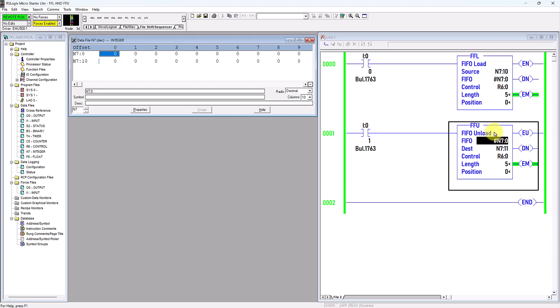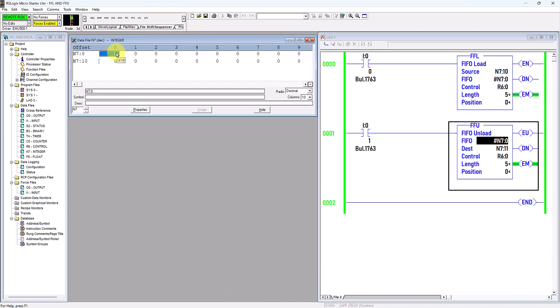As for FFU, or First In First Out Unload instruction — when being energized, the value from the FIFO file address N7:0, which has about 5 words of length, will be unloaded to the destination integer N7:11. In other words, FFU when energized will unload the value from the file address N7:0 to the destination address N7:11.